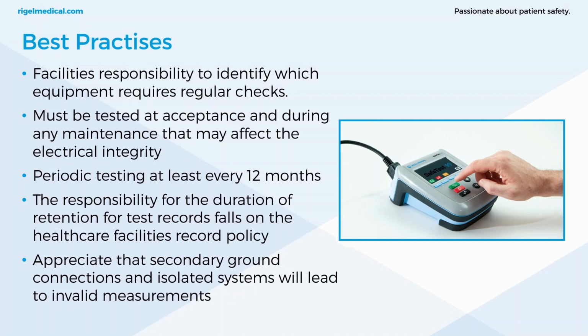However, the responsibility for the duration of retention of test records always falls on the healthcare facility's record policy. And I pulled this directly out of the code, NFPA 99 code. It does fall on the healthcare facility's record policy. Now, this is where alternative maintenance procedures, the periodic testing can vary widely once you've got evidence of safety and reliability of the devices that are in your workshop. So periodic testing may vary to this, as long as you've got evidence that proves that and you've got it in your risk management policy.